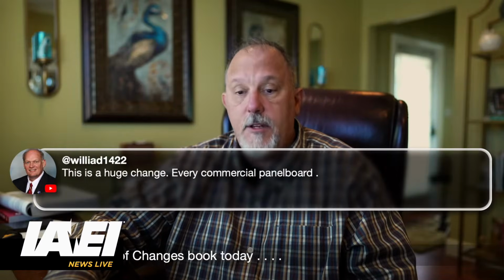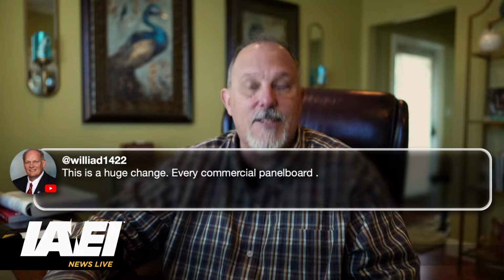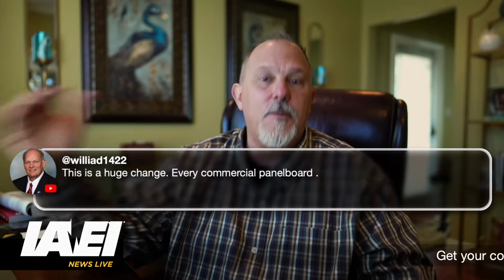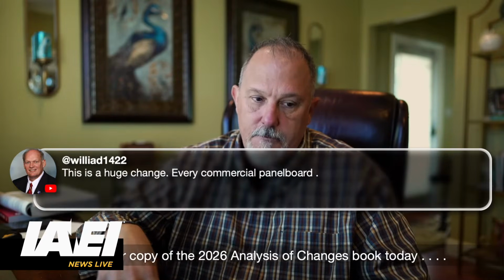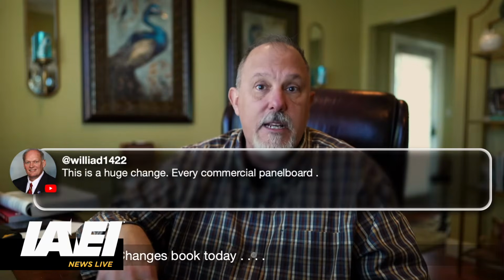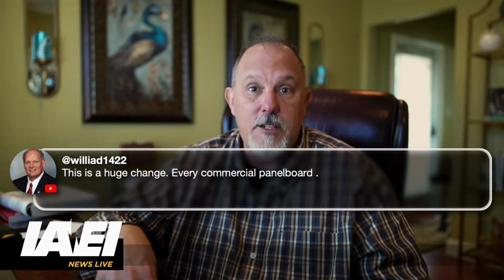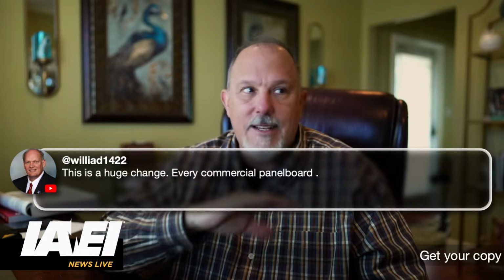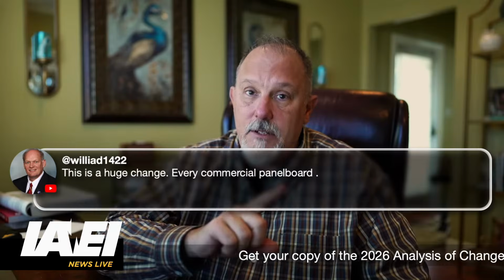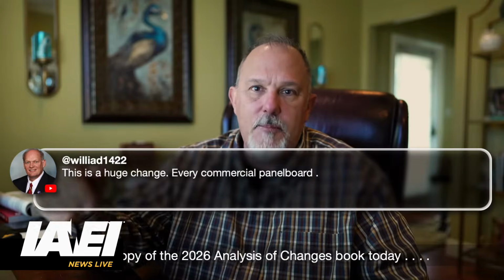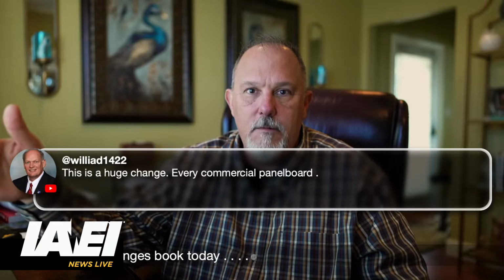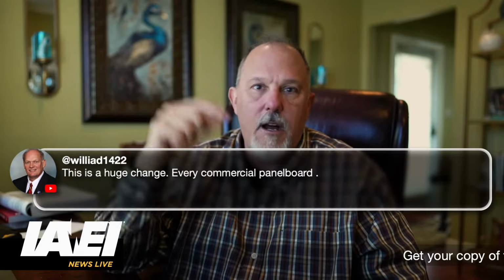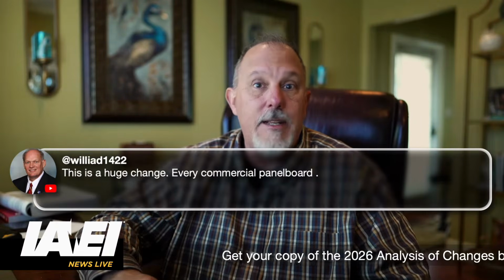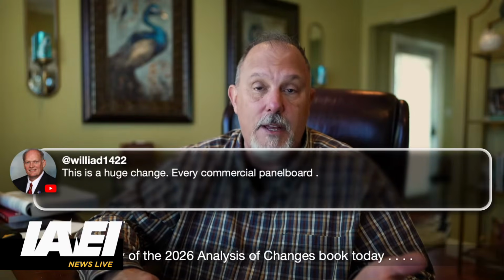Every commercial panelboard, absolutely. Panelboard, switchboard, disconnect. So here's the other issue, and this is the other issue that I've heard, which I'm expecting public inputs on. A 60 amp disconnect switch, a 30 amp disconnect switch. Those are feeder supplied. It doesn't have to be 1,000 amps and above because they took that out. Say it's a 30 amp AC disconnect on a strip mall. That disconnect switch meets the gates of 110.16, and it would be single phase instead of 3-phase.